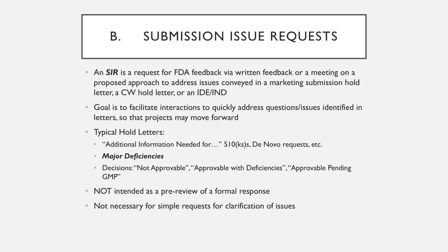Now, moving on, another type of official interaction with the FDA might come in the form of a submission issue request, which happens after some pivotal submission period, like applying for an IDE, where a medical device manufacturer is requesting specific feedback from the FDA in the form of either written feedback or a meeting, and that has to be requested by the device company, on any proposed approaches to address deficiencies within the submission process. So that way, whenever the FDA has requested their specific deficiencies or limitations with the submission that has been made with them, the company and the FDA can come to a quick agreement on how best to resolve those.